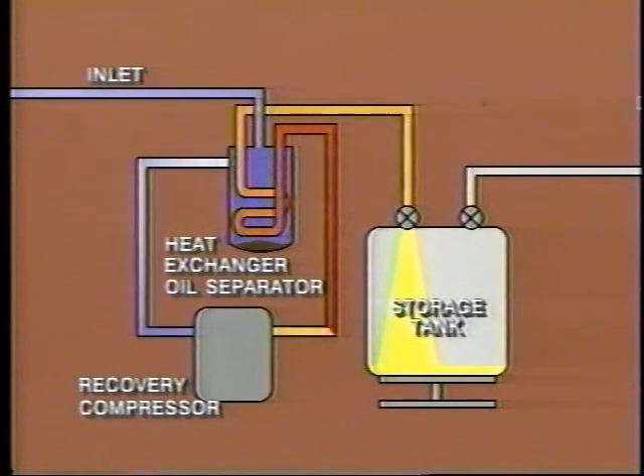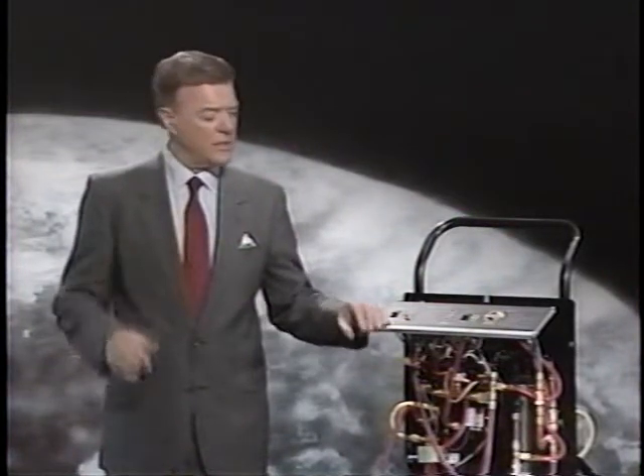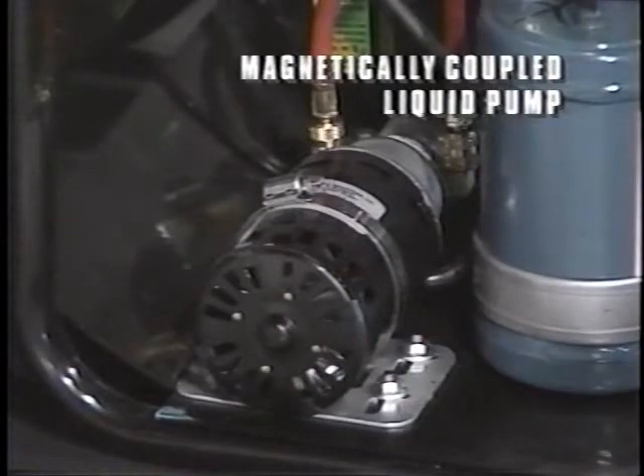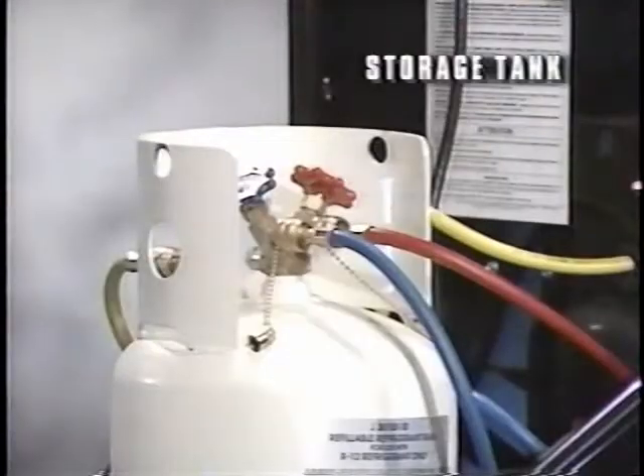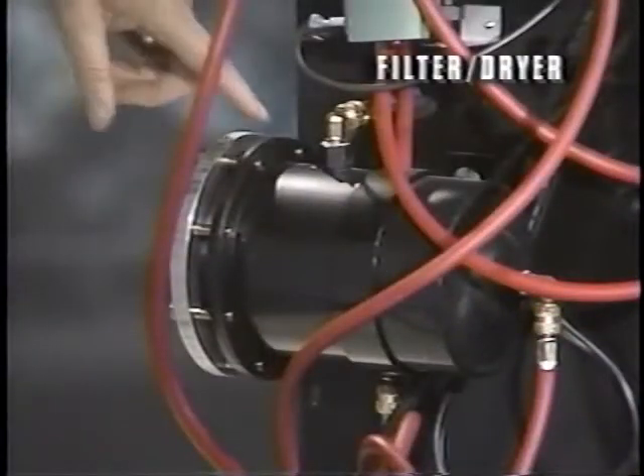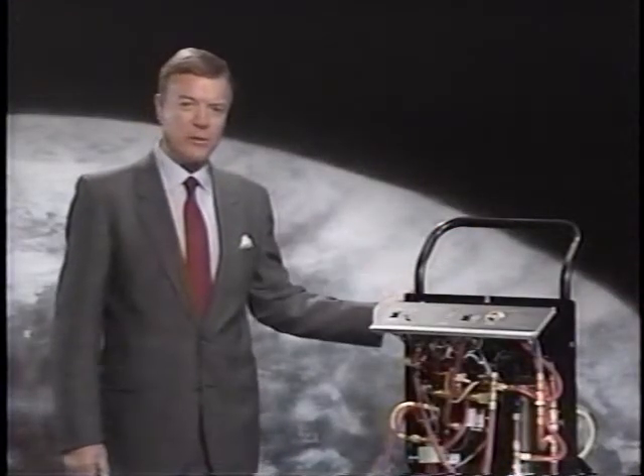R12 liquid flows into the refillable storage tank, and that's the recovery phase. Now, let me show you the recycling phase. It starts at this side of the control panel and goes on to a magnetically coupled liquid pump, the storage tank, a filter dryer, past the moisture indicator, and back to the storage tank. The R12 must remain liquid during recycling, since heat easily boils R12.